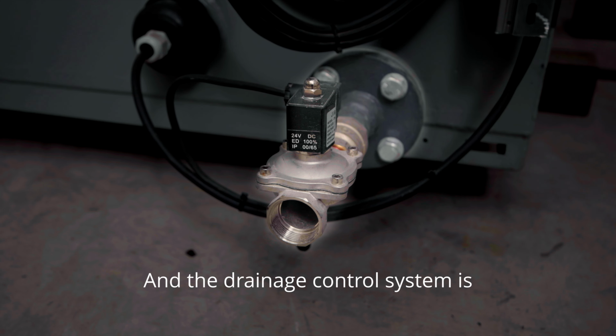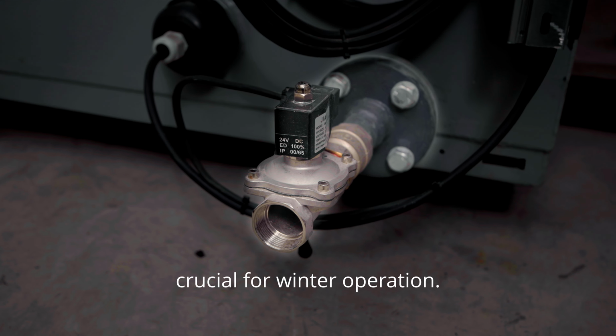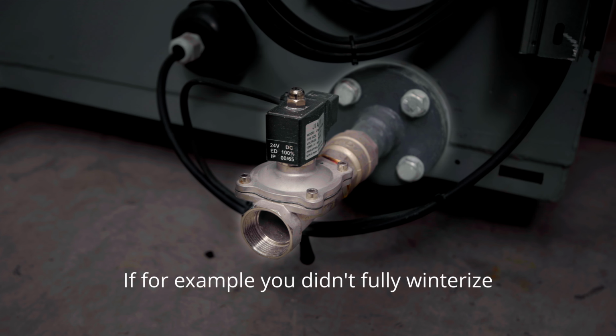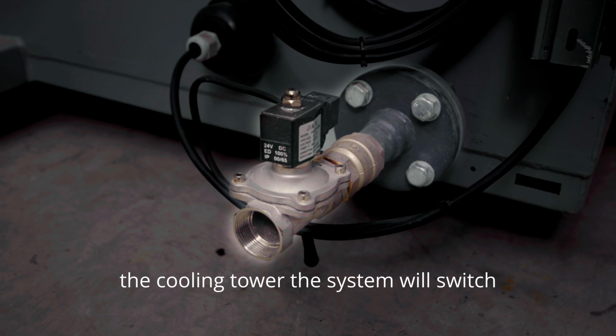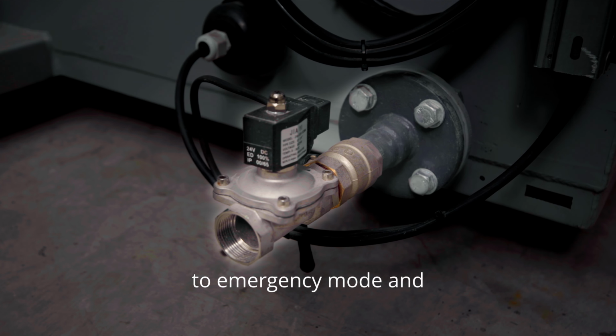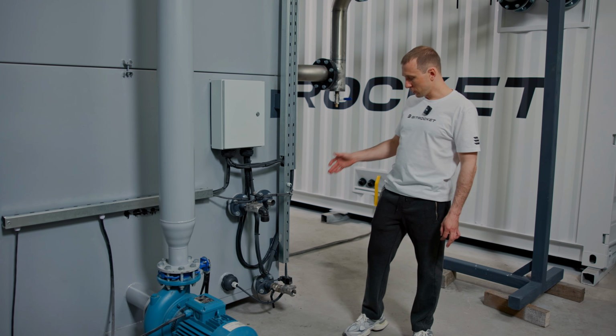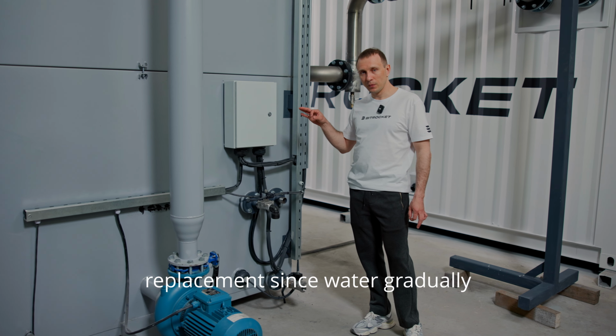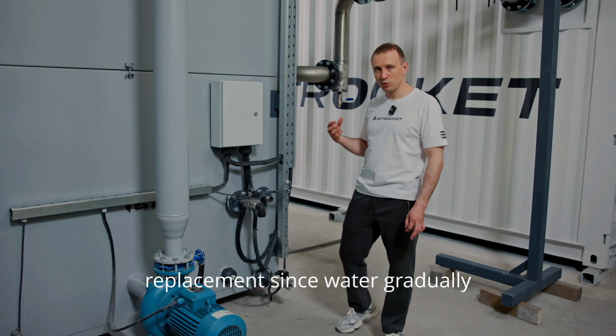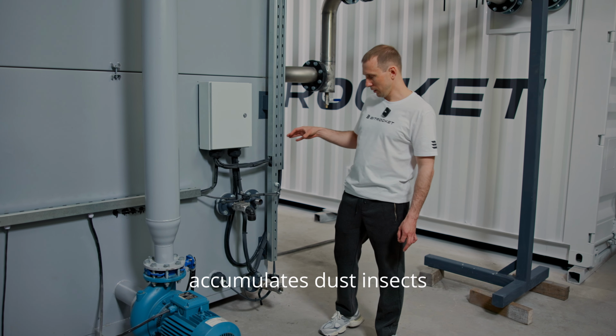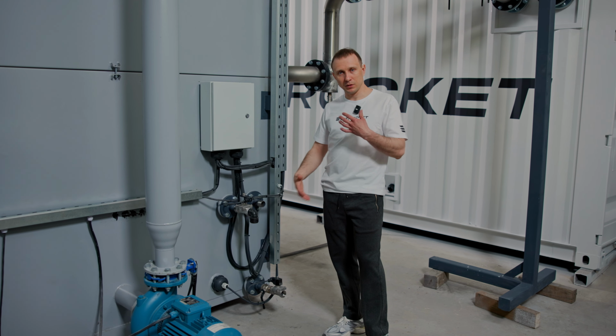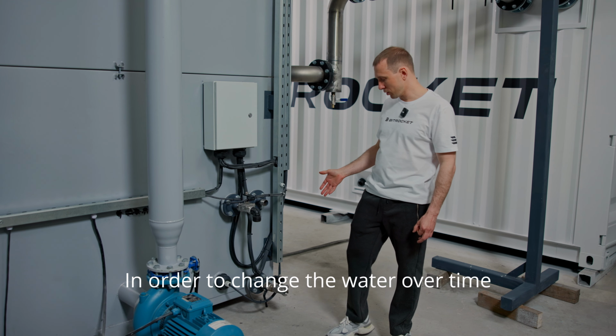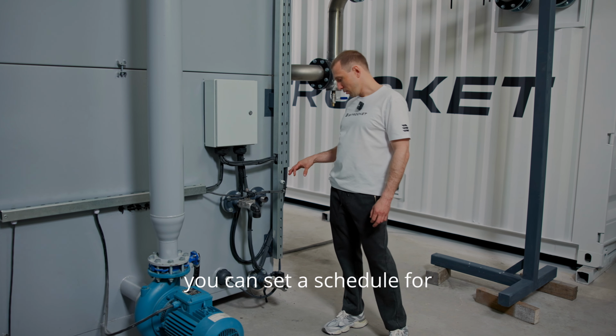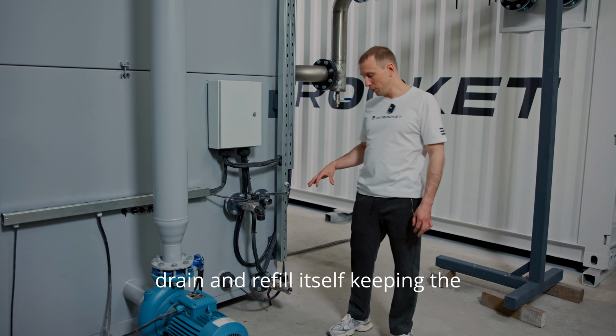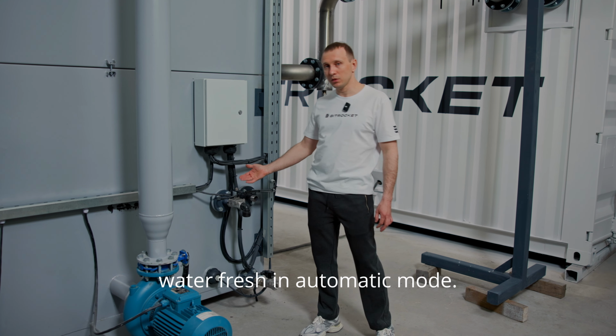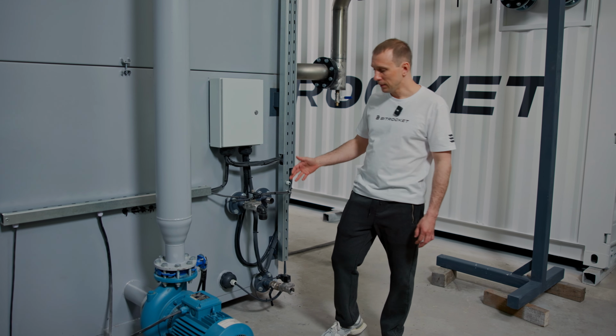And the drainage control system is crucial for winter operation. If, for example, you didn't fully winterize the cooling tower, the system will switch to emergency mode and drain the remaining water. It's also used for regular water replacement, since water gradually accumulates dust, insects, and impurities over time. In order to change the water over time, you can set a schedule for the system to periodically drain and refill itself, keeping the water fresh in automatic mode.